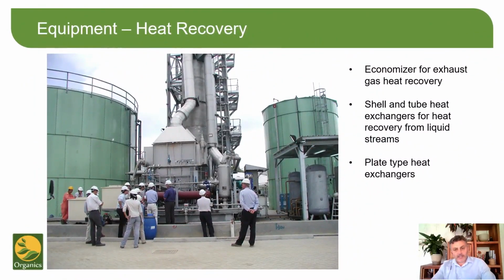Once we've generated the heat, we need to move it to where it is needed. Obviously, the recovery of heat is critical to the process, and as a result, we've become quite expert in where best to target our heat recovery. When looking at the system as a whole, there is a balance to be struck between startup time and heat recovery. Although our primary heat recovery unit is the economiser that takes heat from the combusted gases in the thermal oxidizer, we also recover heat from the exiting process streams.